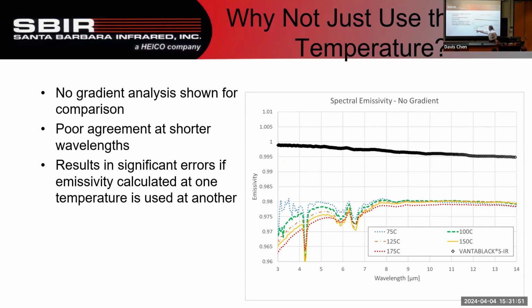So if I tried to do my calibration down here at 175, where it's hot and I've got lots of data at the short wavelengths, then if I were to actually use that at a lower temperature, you actually get a bad calibration, and you can be off by several percent. And our customers are usually looking for something like 1% or less error total with everything. So we try to keep the radiometric calibration to within 0.5% or less.